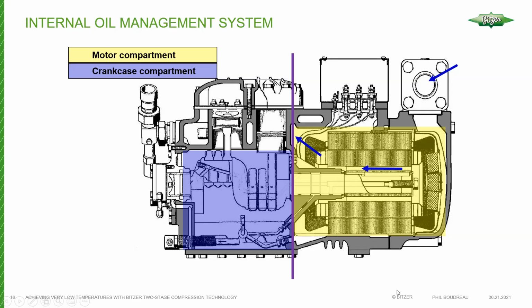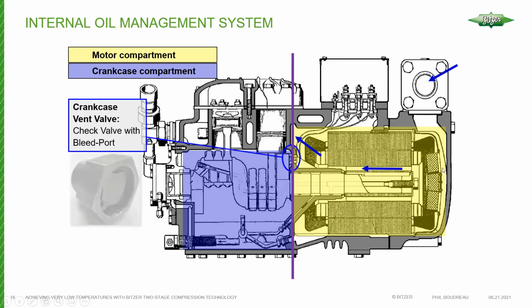And what I'm showing you is the view of a single stage. This isn't meant to be confusing, but the idea is really just to show the partition and the vent valve. The only difference here is this slide really should be modified to show that this is the interstage mixing pipe coming in. So let's call this interstage flow, okay, from your low stage cylinders, comes in, absorbs the heat from the motor, and then into the high stage cylinder.